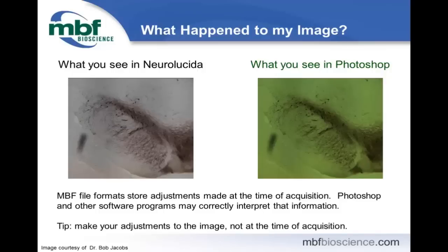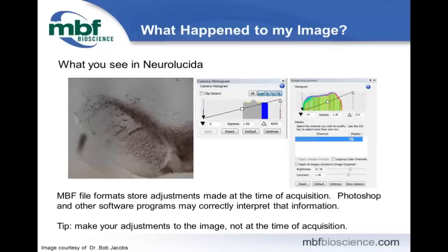MBF offers file formats that store your adjustments separately from the image itself, and Photoshop and other programs may not correctly interpret this. You might have a beautiful image in Neurolucida, but when you open the same file in Photoshop it may be a different color or have incorrect contrast. We recommend keeping your camera histogram with the full dynamic range and then making necessary adjustments in the image adjustment window after acquisition, rather than at the time of capture.